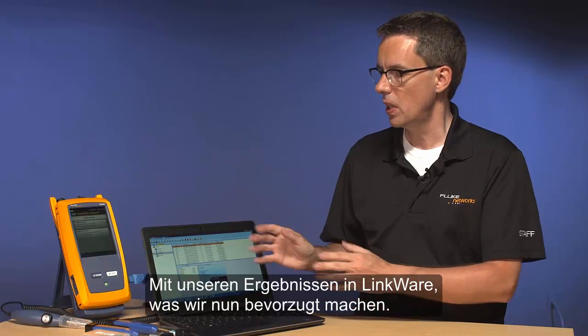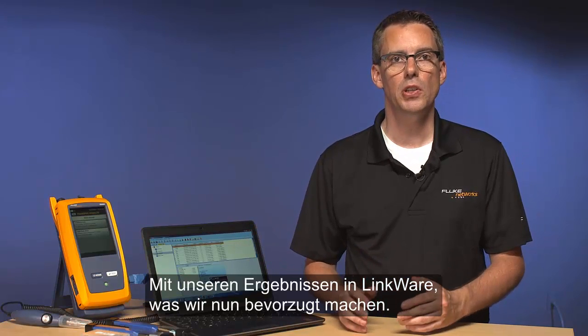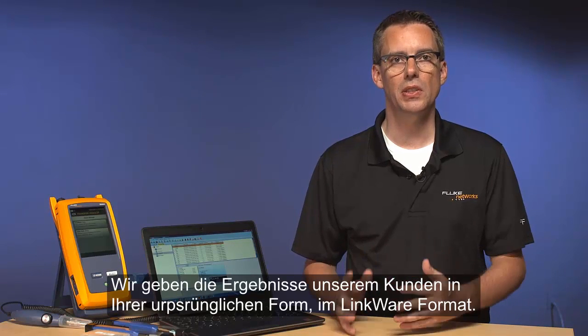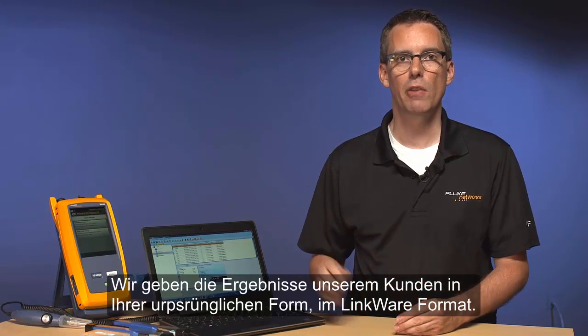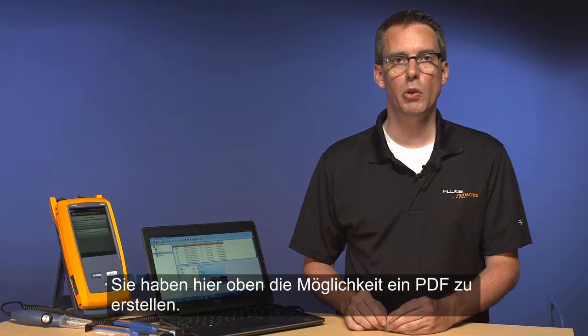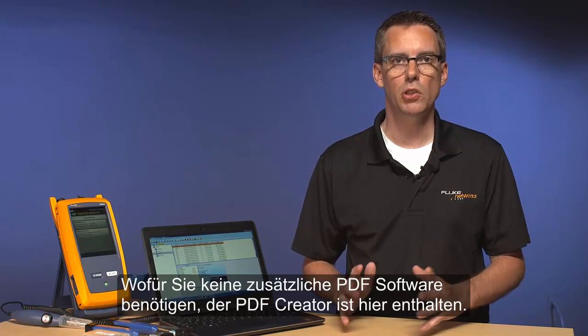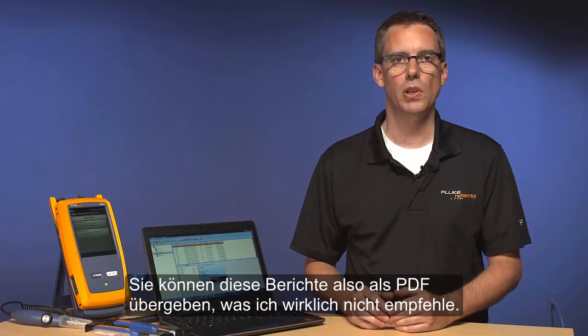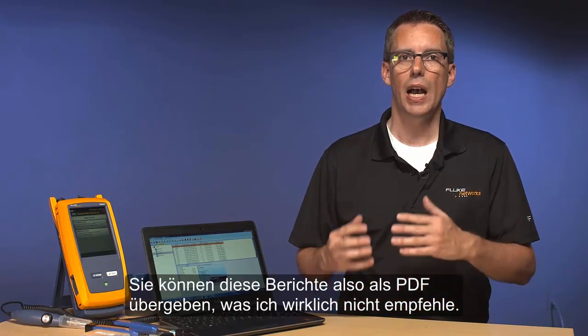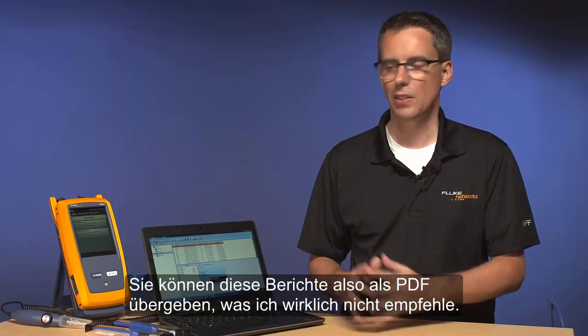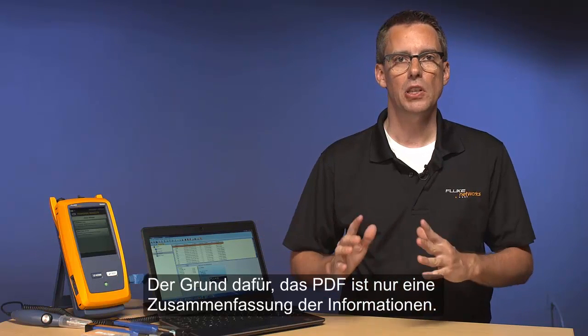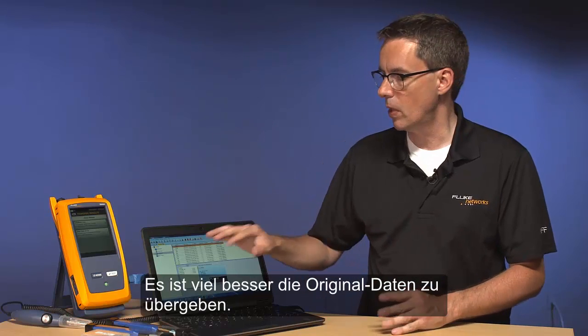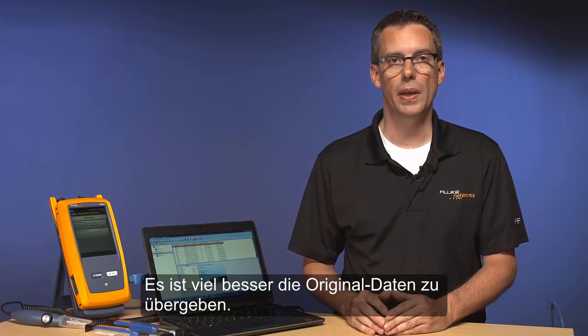So with our results in LinkWare, what we prefer to do is give the customer the results in their native format, that is in the LinkWare format. So save it, and you'll save it as a .flw file. You do have the option up here of creating a PDF, and you don't need PDF software. The PDF creator is built into here, so you can hand those results off as a PDF. I highly recommend not doing that. The reason why is the PDF is a summary of the information. It's much better to have the original data on there.